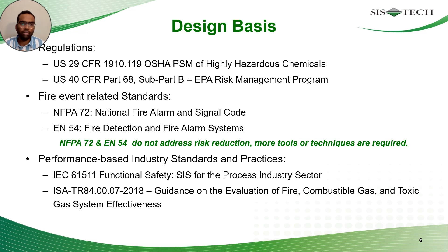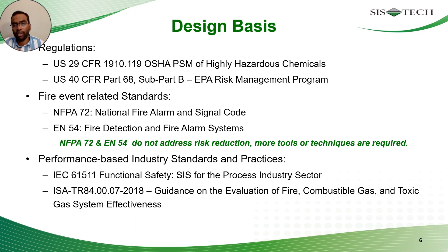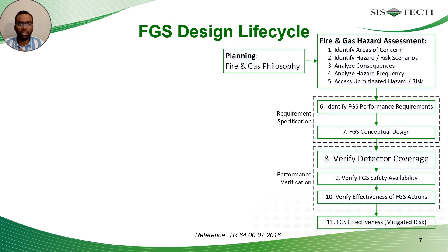We have a performance-based industry standard — IEC 61511 — used for Safety Instrumented System (SIS) design for the process industry sector. Using the same underlying principles, ISA has published technical report TR84.00.07, which provides guidance on how to evaluate the effectiveness of identified FGS functions. These guidelines and principles can be effectively used in conjunction with good engineering practices. Due to the challenges in achieving FGS effectiveness, we recommend assigning the minimum possible risk reduction credit to the fire and gas system.